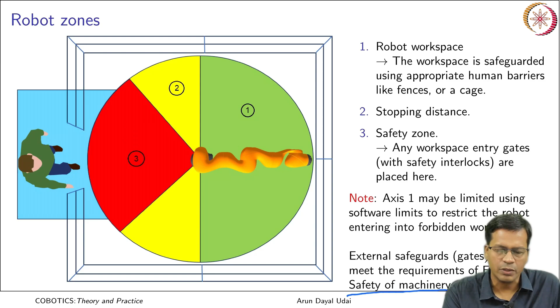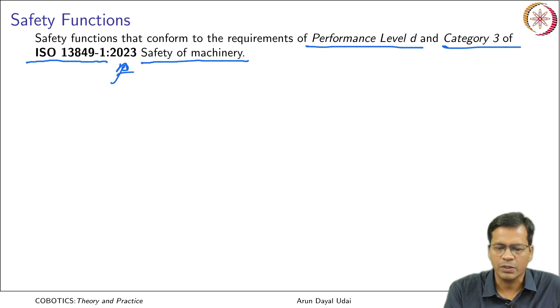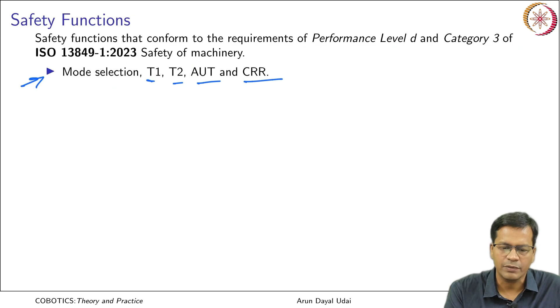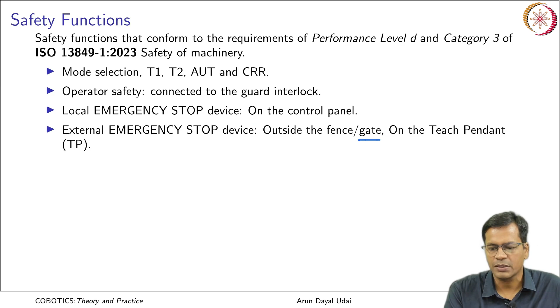Safety functions conform to the requirements of performance level D, category 3 of ISO 13849-1, that is for the safety of machinery. From time to time this may be revised with some modifications. That decides the mode selection, T1, T2, automatic or CRR mode, that I have discussed. Operator safety is connected to the guards and the interlocks. There is a local emergency stop device on the control panel, on the teach pendant also. An external emergency stop device is outside the fence or the gate. TP is for teach pendant. The emergency stop on the teach pendant is counted as an external emergency stop.